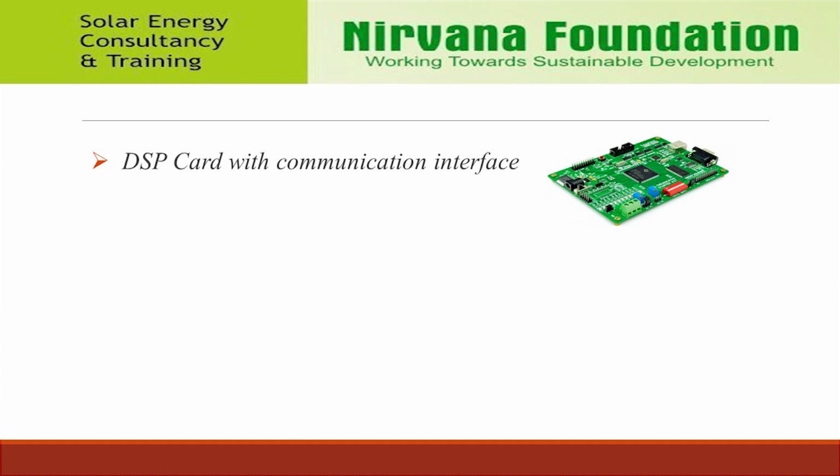DSP card with communication interface. By DSP-controlled device we can monitor gate signals to IGBT driver cards. MPPT controller. Tracking grid voltage and synchronizing with grid while exporting. Data logging and communication via RS-232/485 protocol. Temperature sensing and operating cabinet and heatsink cooling fans.